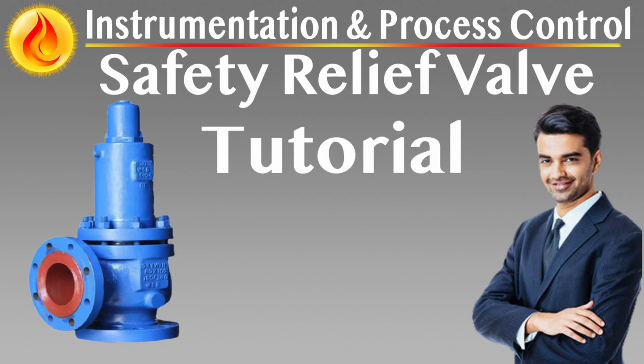Primary application guidelines. Suitable for installations where built-up back pressure remains low and does not interfere with valve performance. Ideal in systems that relieve to atmosphere, flare headers, or low-pressure collection systems. Typically applied when the accumulated pressure, set pressure plus allowable overpressure, is not exceeded by back pressure effects.